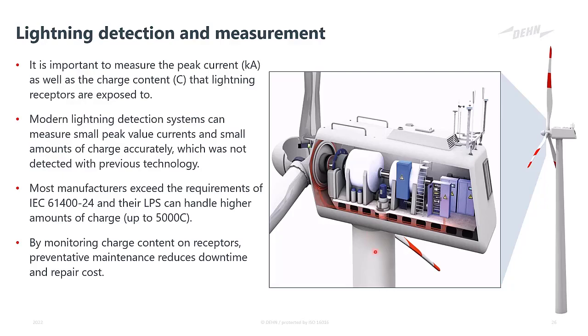The lightning, as we mentioned, travels up from the base through the tower into the nacelle, out through the blade, and it goes up into the clouds with an upward strike. Now, the nacelle and the entire wind turbine, as we said, is manufactured according to lightning protection level 1. So there are very strong reinforced carbon brushes around bearings in the nacelle and across the yaw, and this is able to carry the lightning current to the point where it leaves the lightning protection system. And modern lightning detection systems are then installed inside. They could be installed around the base or the tower or around the shaft, and they measure the current traveling through this system out via the blade.